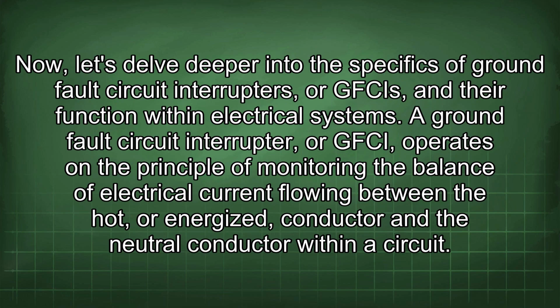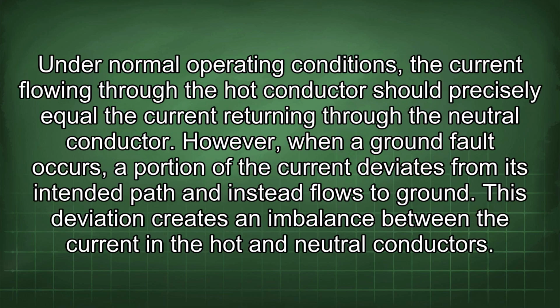Now let's delve deeper into the specifics of GFCIs and their function within electrical systems. A GFCI operates on the principle of monitoring the balance of electrical current flowing between the hot, or energized, conductor and the neutral conductor within a circuit. Under normal operating conditions, the current flowing through the hot conductor should precisely equal the current returning through the neutral conductor. However, when a ground fault occurs, a portion of the current deviates from its intended path and instead flows to ground. This deviation creates an imbalance between the current in the hot and neutral conductors.